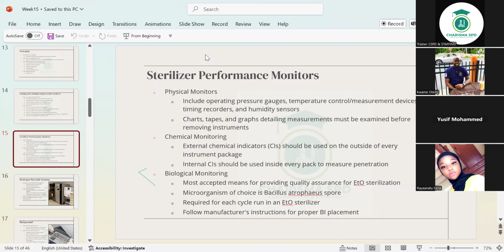The chemical monitoring is there too, where we have those paper strips and indicators that we put in the instruments. We put them in the hard to reach areas to make sure there's real penetration so it comes out properly conditioned. We look at it and the IFU tells you this indicator must change all through. Maybe it's 3 inches long with that strip on it. If it changes 2 inches and the tip has still not changed to the color specified by the IFU, it's not correct. It didn't do it right. Something has to be done again.